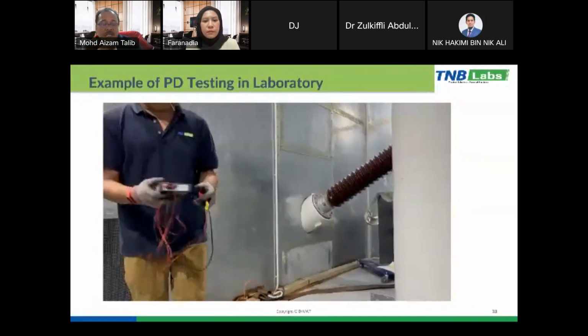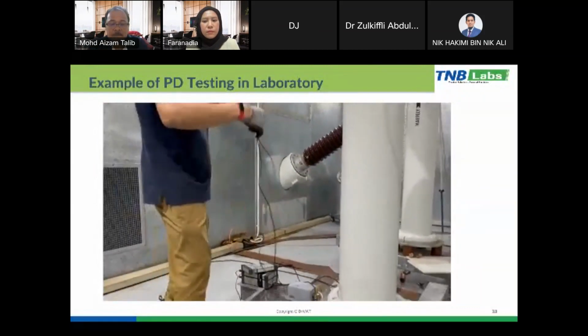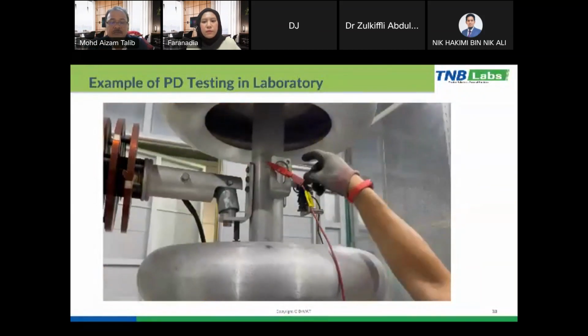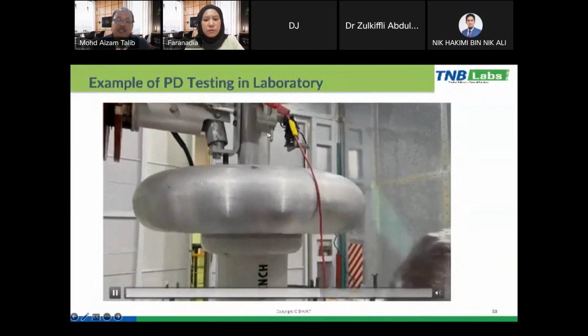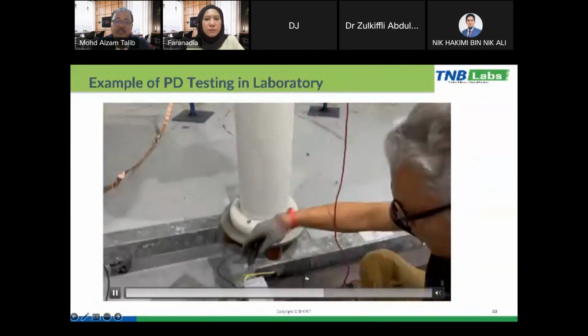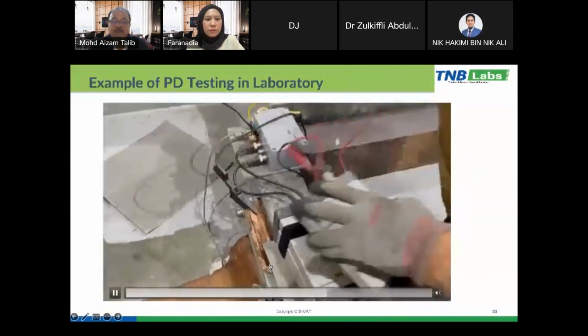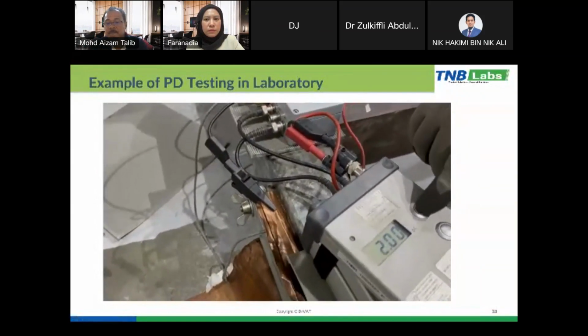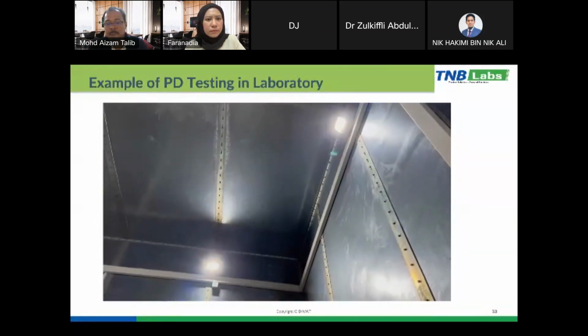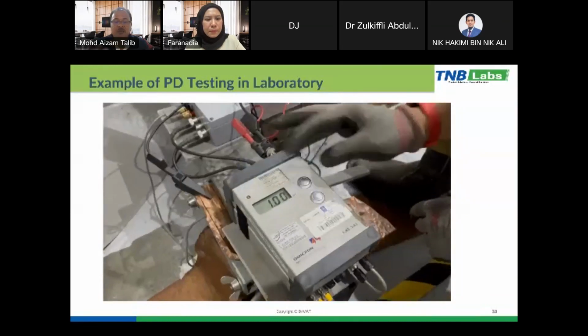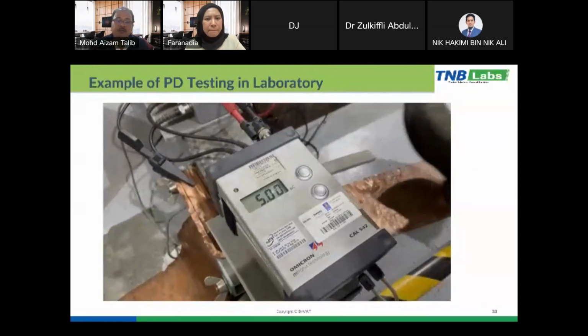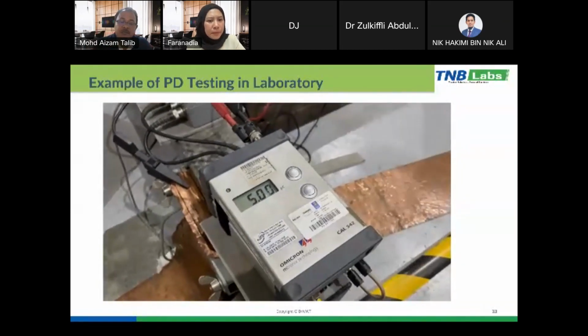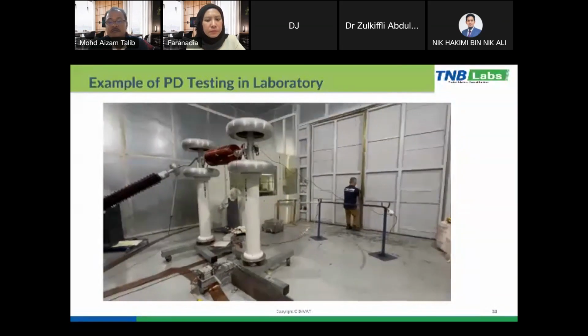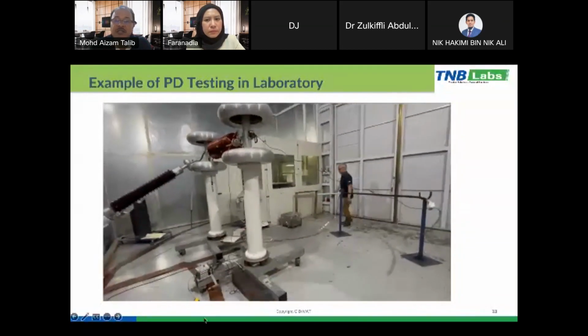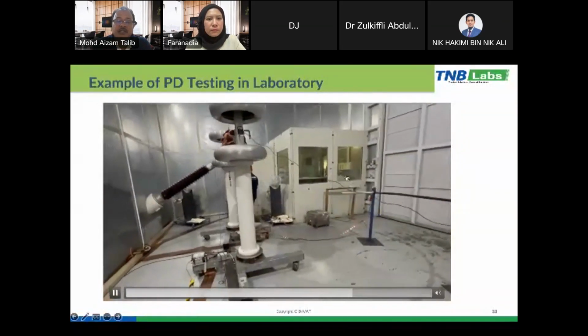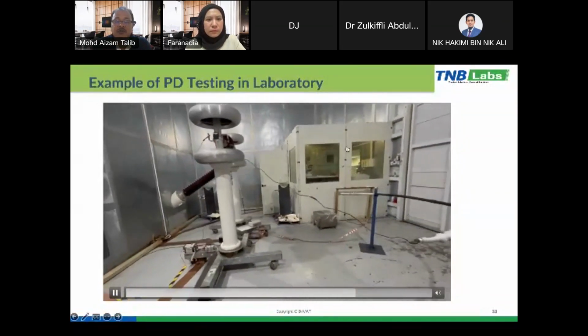Okay, we use the calibrator. We put it at the HV terminal, and the other connection we put at the ground terminal. Okay, this is our shielded room. Let's say we inject the PD pulse at 5 picocoulomb. So this is our shielded room or Faraday cage. And here this is our control room.